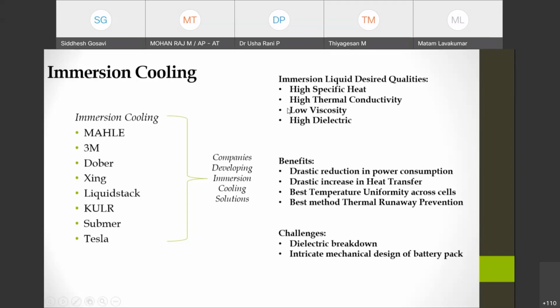Speaking of the immersion liquid's desired qualities: it should have high specific heat, high thermal conductivity, and low viscosity, because I want power consumption to be very low. And the most important among all is high dielectric strength, because it doesn't only depend on the voltage—800 volts and all.